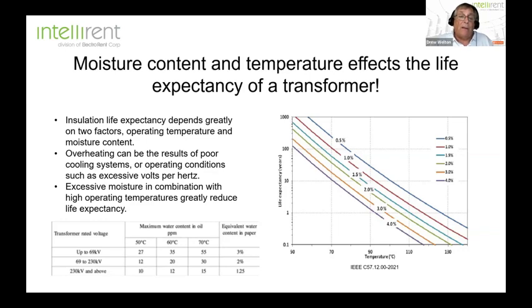So what IEEE tells us is that you must take care of moisture. You must do what you have to in order to mitigate moisture in the transformer based on these levels. In terms of ppm in your oil sample, depending on the size of the transformer, you can see the limits here. But what we really want to be concerned about is the equivalent water content in the paper itself, because that's where it does the most damage.